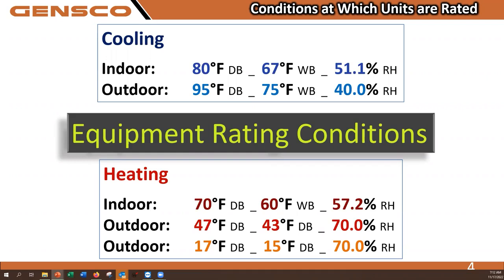Now, if the air is cooler, that does not derate the unit. But if you're living somewhere on the east side, the mountain area, the desert area, and you get above 95 degrees, you begin to derate the output of that unit. In fact, once you exceed 100 degrees, the derate starts to escalate, and it can get very substantive. You hit 105, 107, you may have lost 15, 18% of your cooling capacity. Heating units are rated at a 70-degree return air temperature. And of course, at outdoor temperatures of 47, you'll find a rating, and generally at 17, you'll find a rating.